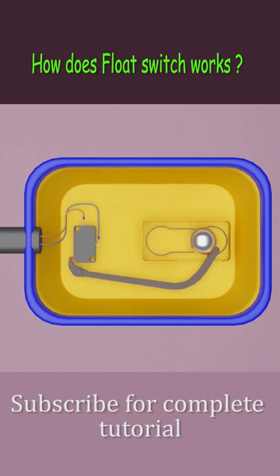Now when the water level rises, the float switch moves upwards and its metallic ball moves backwards, and it releases the lever, and the micro switch resets again and its contacts become closed again.